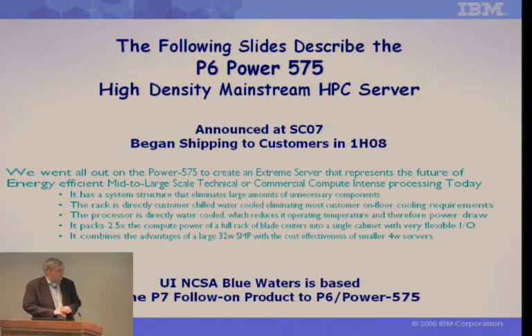So a lot of effort went into making this as energy efficient as we could - trying to gather up a number of system components so we can combine them on fewer components instead of many. Chill water cooling, which I'll talk more about, took the cooling directly to chill water rather than going through a couple of stages in the data center. Processors directly water-cooled took us another step further, with lower temperature and lower leakage power.